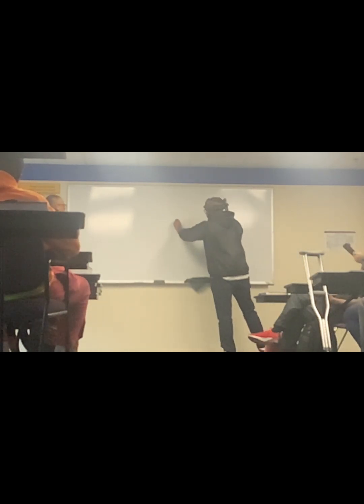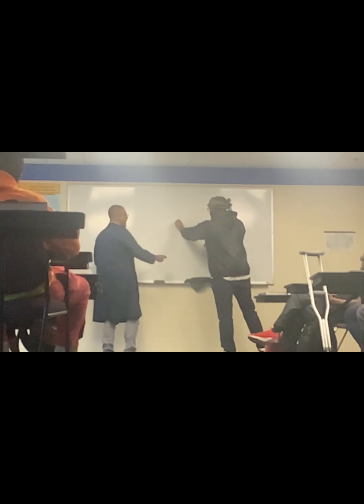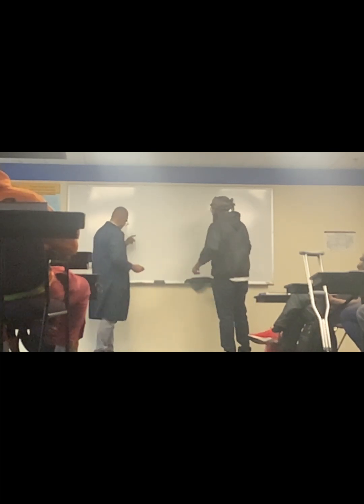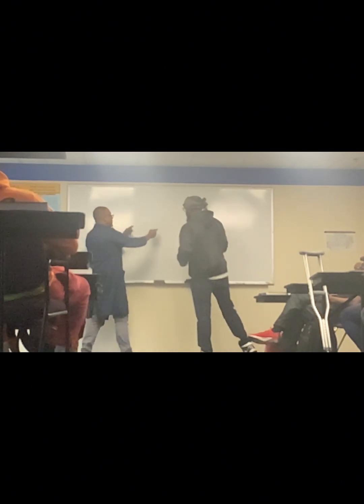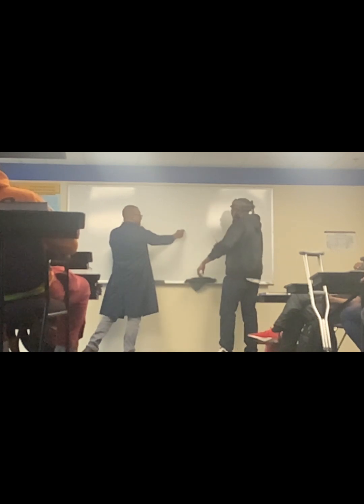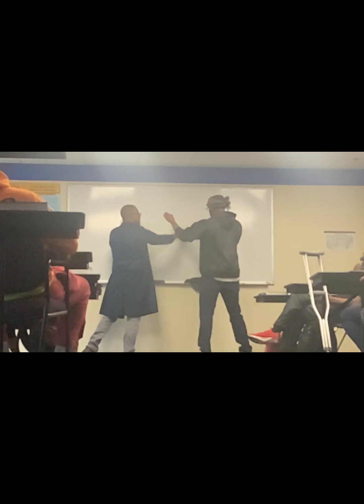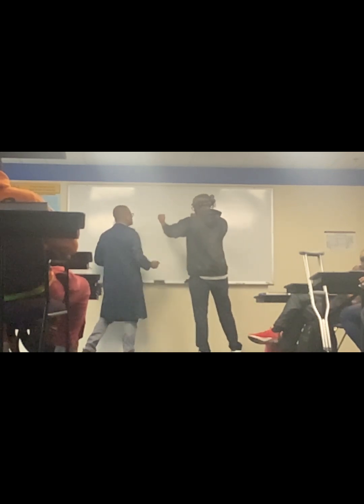Well, I'm confused with what you did. You did this one and this one. Yes, L2 to ground. That's to the ground. You did 120. The same thing for this side, 120 if it's good. But if both of these read 120 together, it's 240. It's 120 to both sides. Yeah, that's 240. And you still can use the black and the red meter. Yep, that's how you do it.